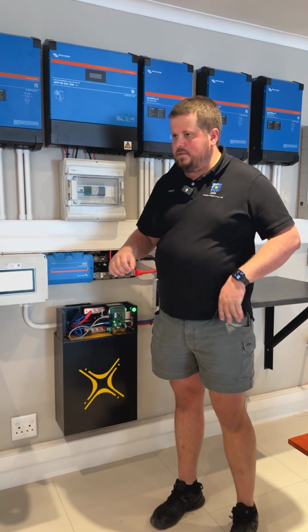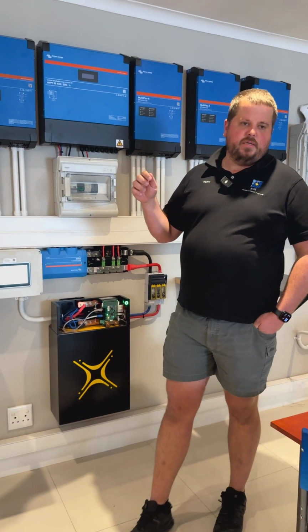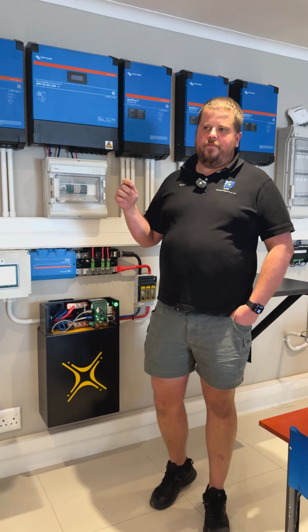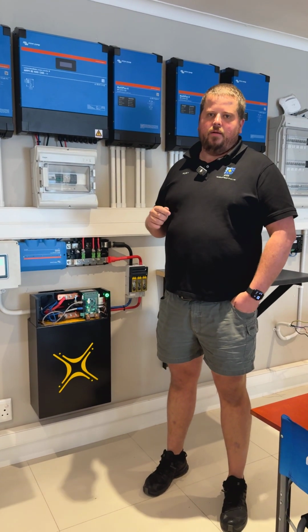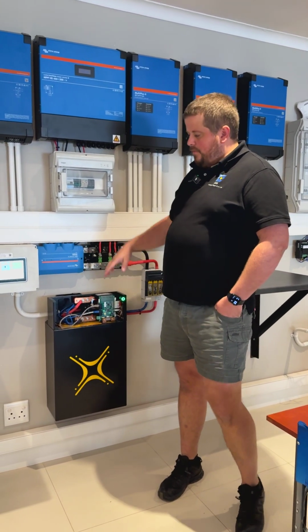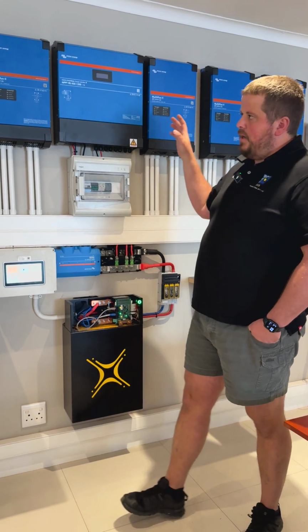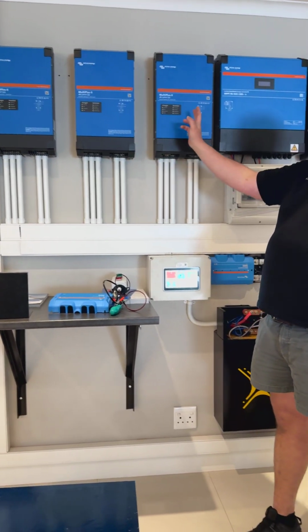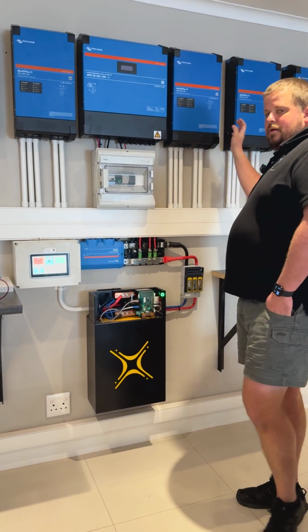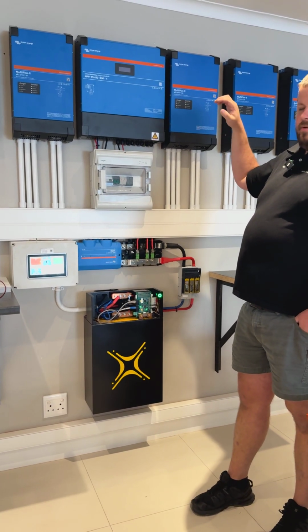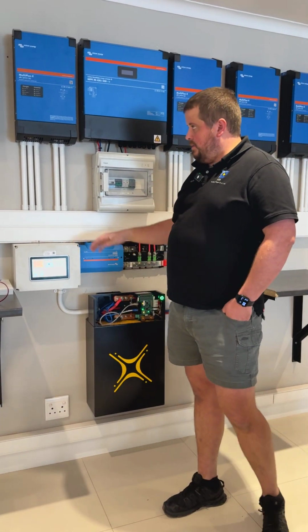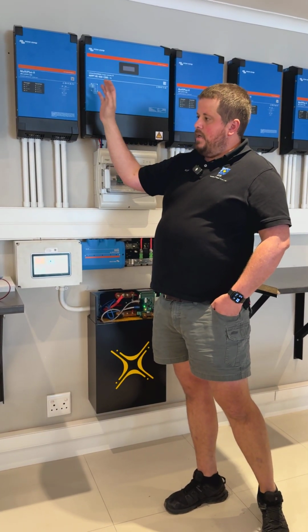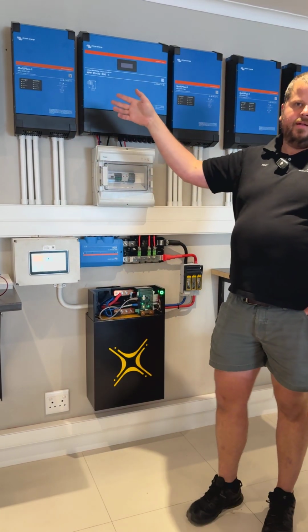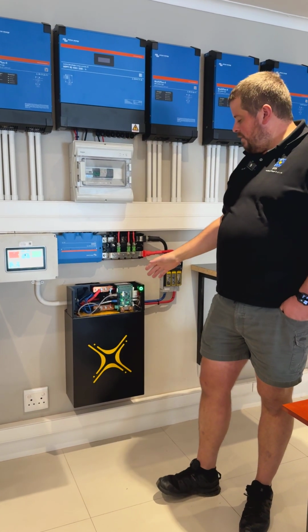We've said on multiple occasions where guys have a 5 kilowatt inverter with a 5 kilowatt battery, this is way out of ratio. I know because this is just for training purposes - this is 9 kVA, 9 kVA. If you go onto the website, you'll see you need at least 36 kilowatts of battery to run this, since this is 18. This is only a 7 kilowatt battery.